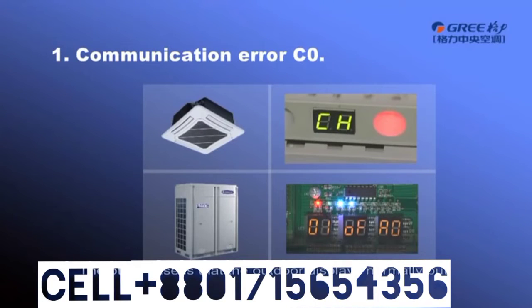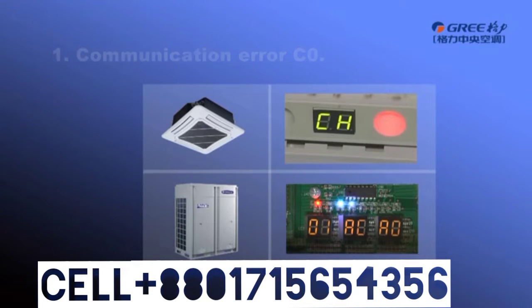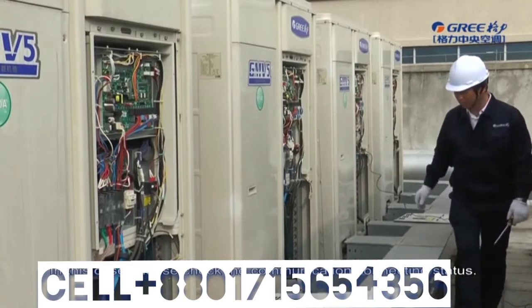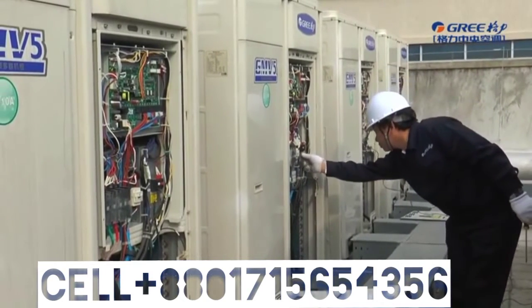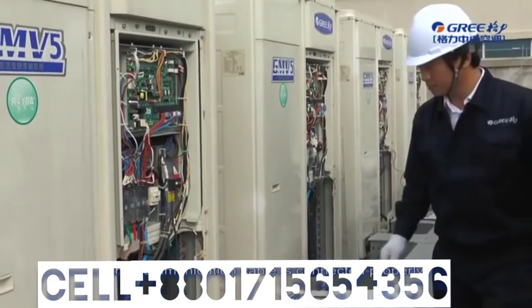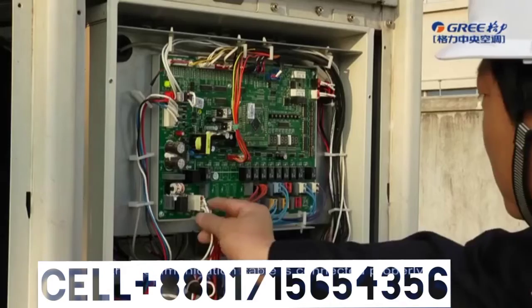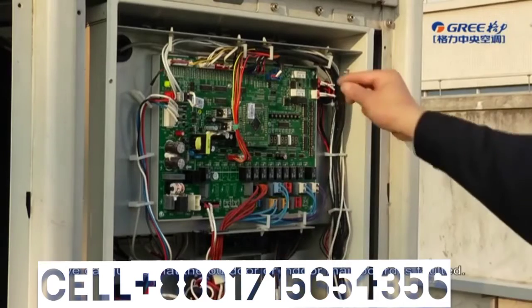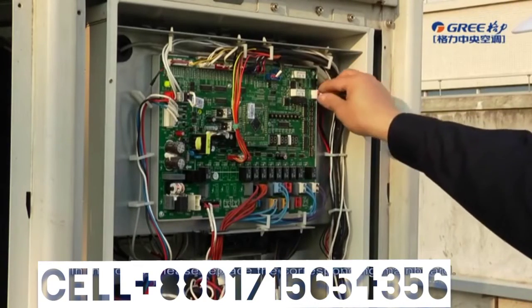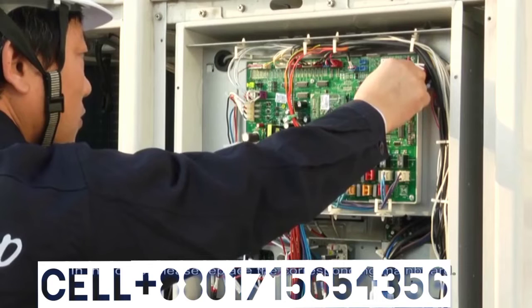The other case is that the outdoor displays normally, but some indoor units display C0, which means the indoor unit with error display is not connected well with the main communication cable, or the wired controller is not connected well with the indoor unit. In this case, please check the communication connecting status. In the two cases mentioned above, if the communication cable is connected properly, we can judge that the outdoor or indoor mainboard is faulted. In this case, please replace the corresponding mainboard.